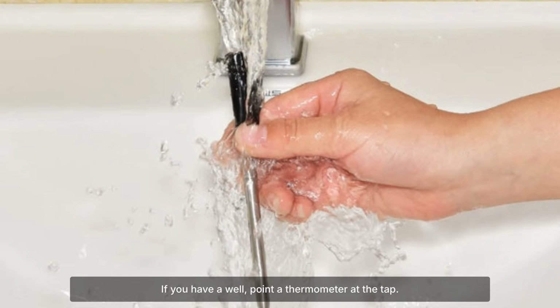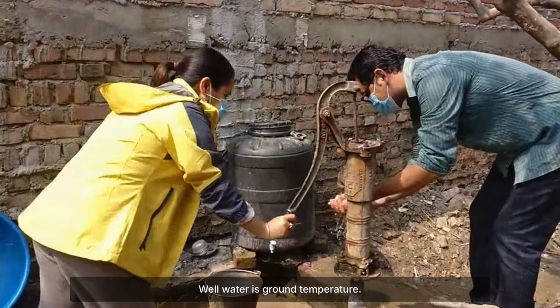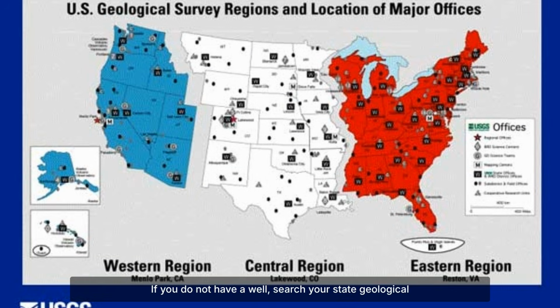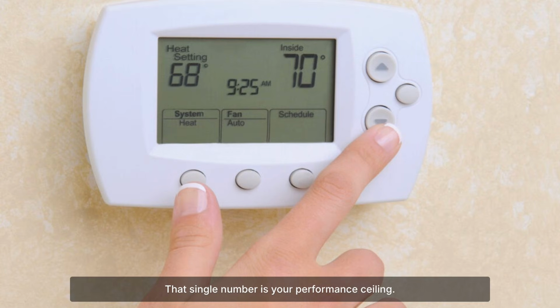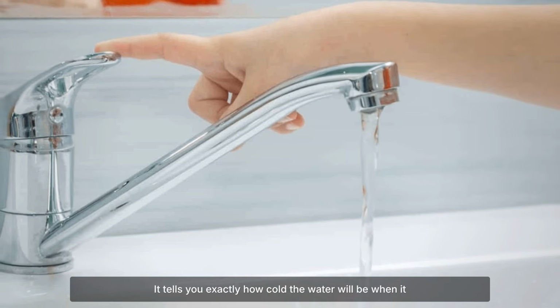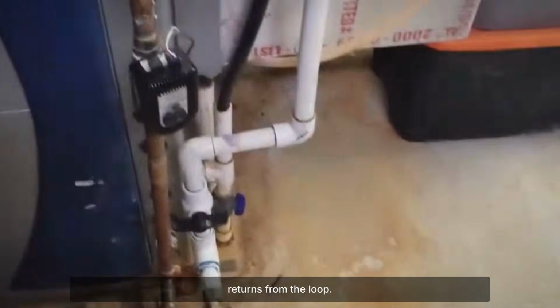If you have a well, point a thermometer at the tap. Well water is ground temperature. If you do not have a well, search your state geological survey for ground temperature data by zip code. That single number is your performance ceiling. It tells you exactly how cold the water will be when it returns from the loop.